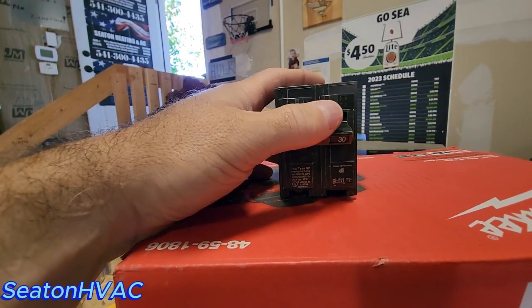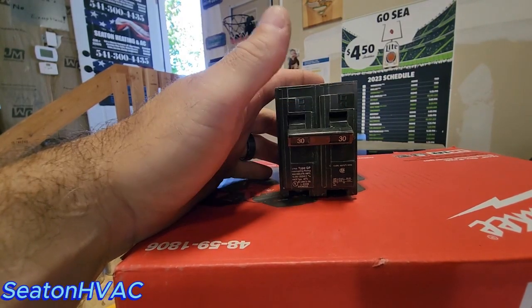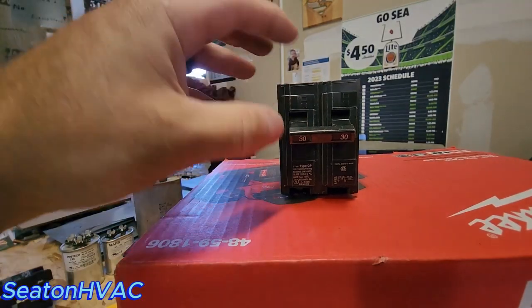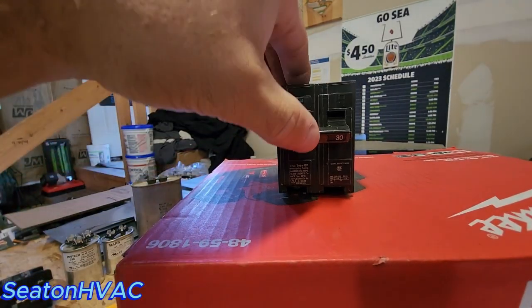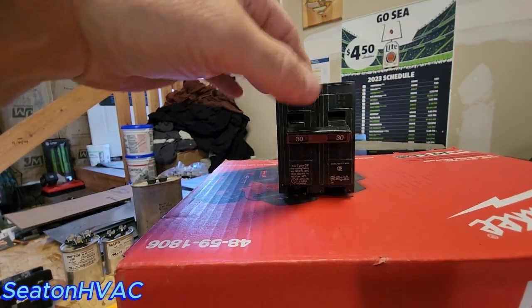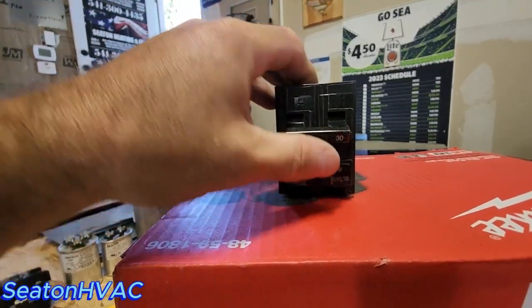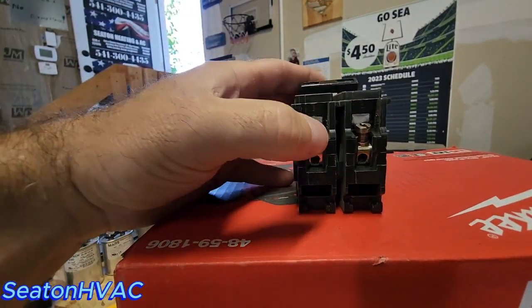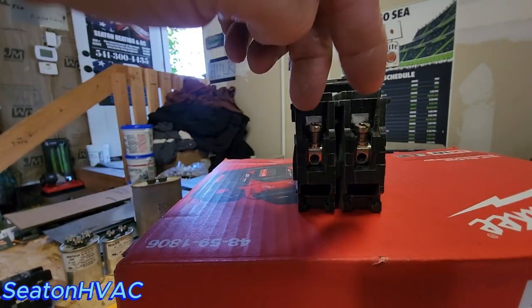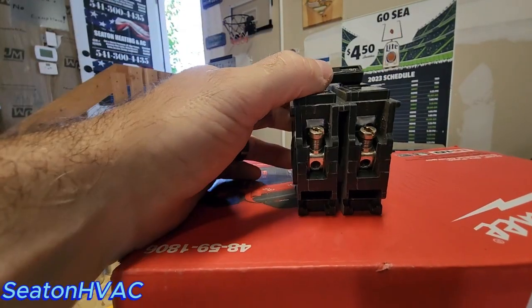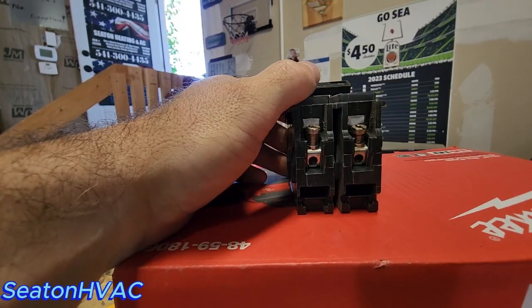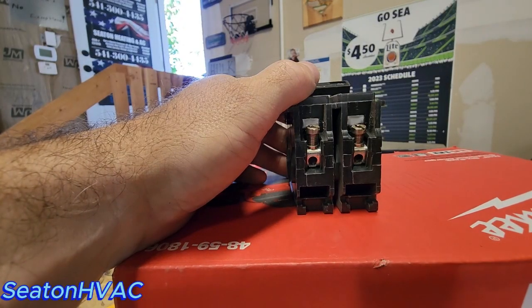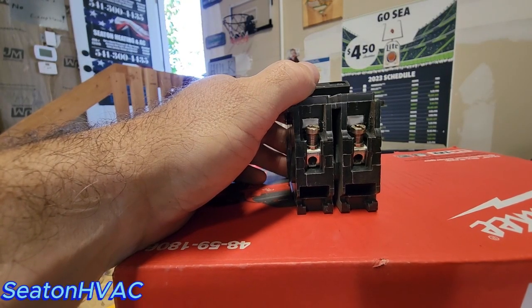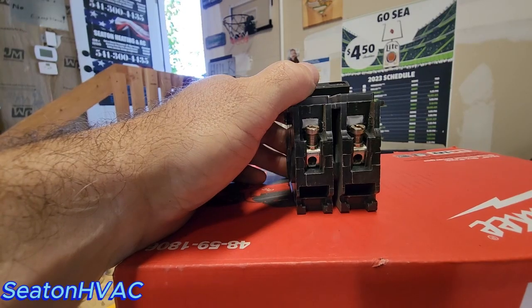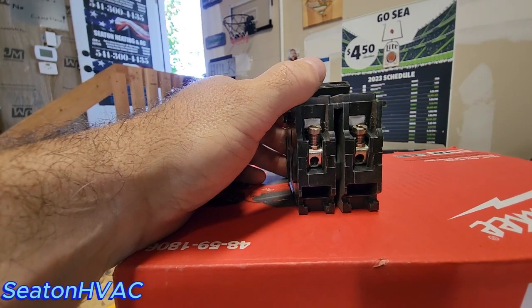So this is what's called a double pole breaker. Okay, 240 volt double pole breaker. So the reason why is you have two poles. One pole here, another pole here. Each one is 120 volts. Together they're 240 volts. Okay. So on the bottom of the terminal you have 120 volts here, 120 volts here, 240 volts, okay? This would be for like an electric furnace, an air conditioner, a heat pump, a fridge, a dryer, a range, something that requires 240 volts in the home, okay?